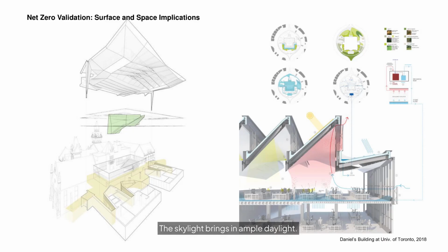2. Reduced through energy-efficient systems. Efficient HVAC strategies include hydronic radiant heating and cooling embedded in the concrete slabs of floors and ceilings. These radiant surfaces and efficient air distribution minimize the fan power and ductwork needed for air conditioning while maintaining a high level of indoor comfort. Geothermal wells on-site coupled with DOAS in mechanical rooms in the basement operate the building with less energy demand. After bioclimatic design and efficient systems are complete, the building operates at a net EUI of 62 kBTU per square foot per year, which is about 40% lower energy use than a typical comparable building.